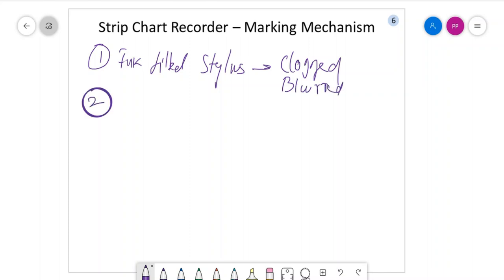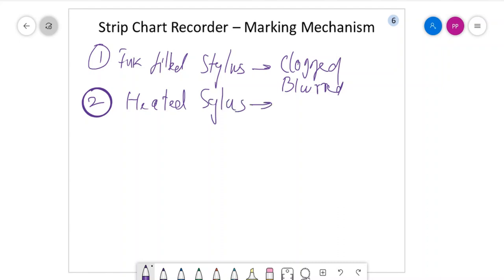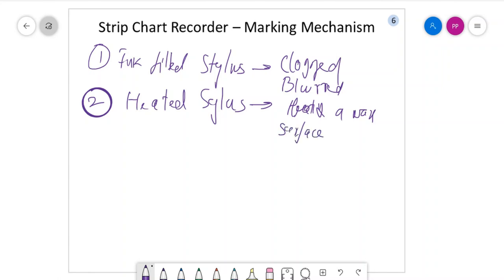To overcome this issue we use the heated stylus. Here you are heating the marking material — basically the stylus is putting its impression on a wax coating of a black paper base. This can respond up to 40 Hz. By heating a wax surface you are leaving the impression, and up to 40 Hz of input signal you can respond.